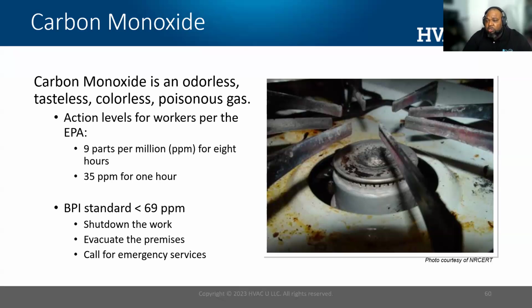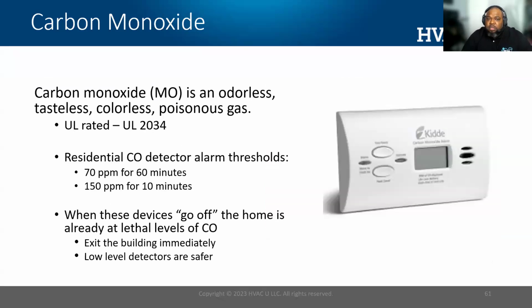Right. So those are some of the numbers you need to take into account for carbon monoxide. Now, just for awareness, to help you understand: when you purchase a carbon monoxide detector, it's UL 2034 approved, which means it's designed to enunciate at 70 parts per million for 60 minutes, or 150 parts per million for 10 minutes.